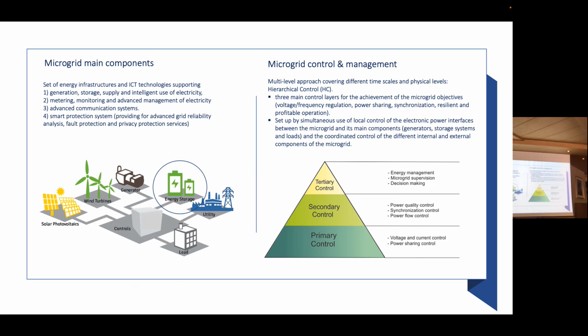From the point of view of control and management, microgrids are usually governed by a multi-layer, multi-level control philosophy called hierarchical control, composed of three main layers: voltage and current control and power sharing among different generators at the lower level, synchronization with the upstream main grid or power quality control at the secondary level, and decision making or microgrid supervision, for example for resilient and profitable operation, at the upper tertiary level.